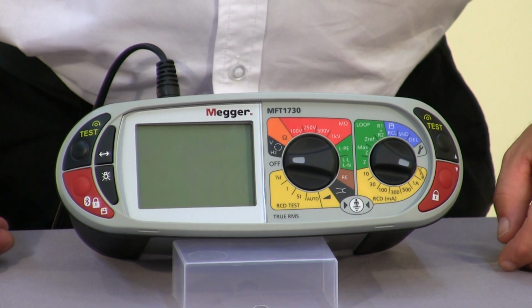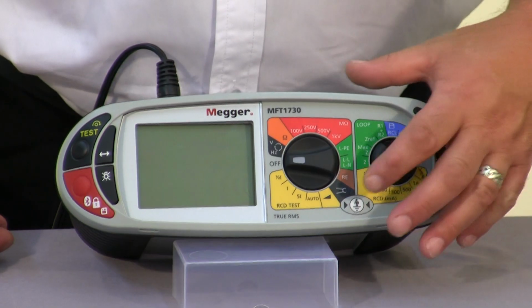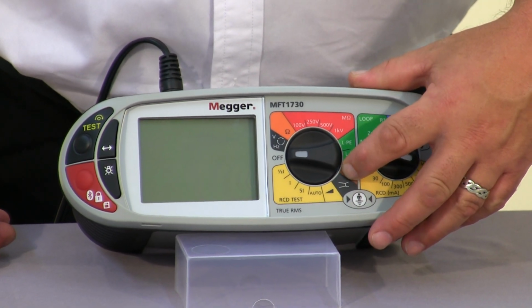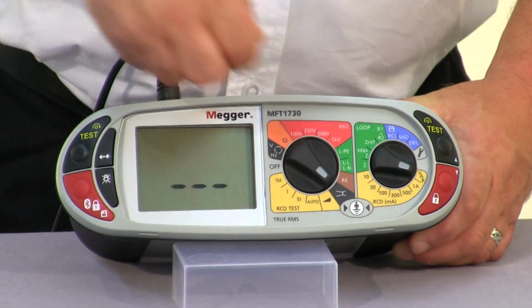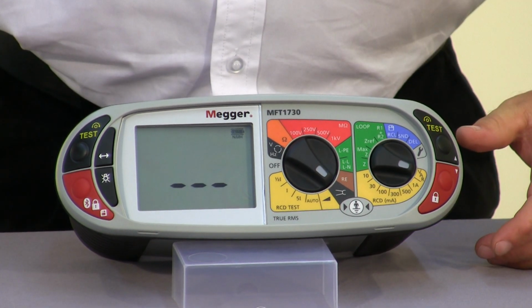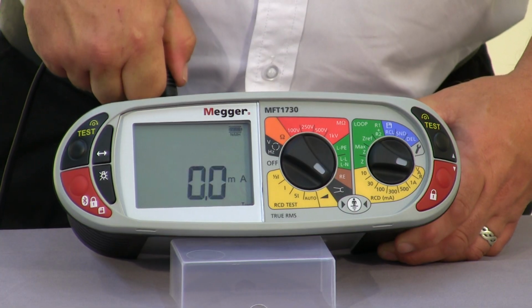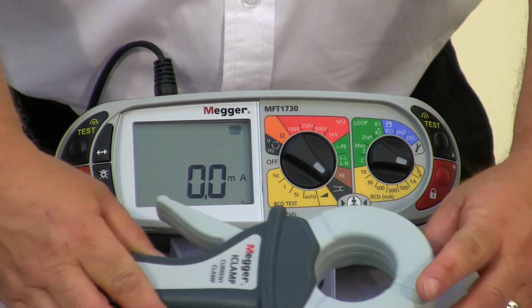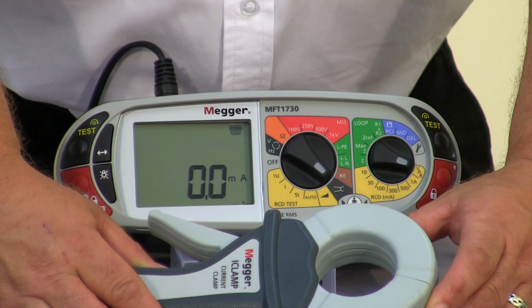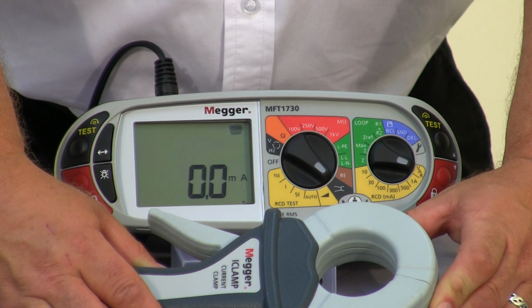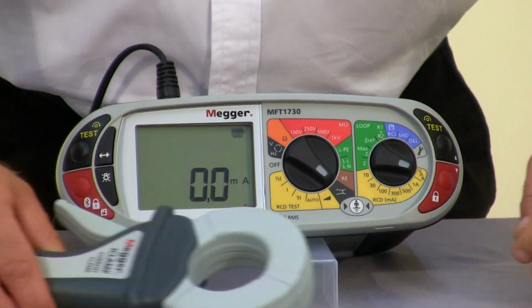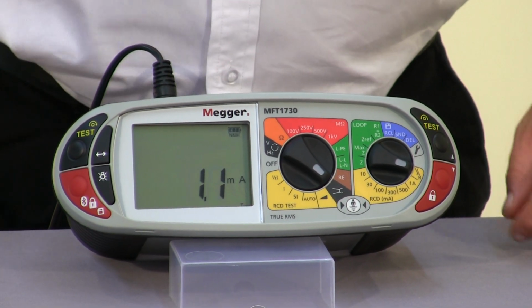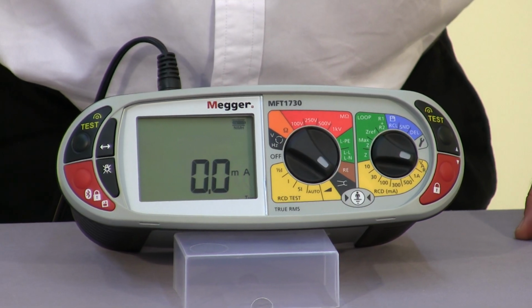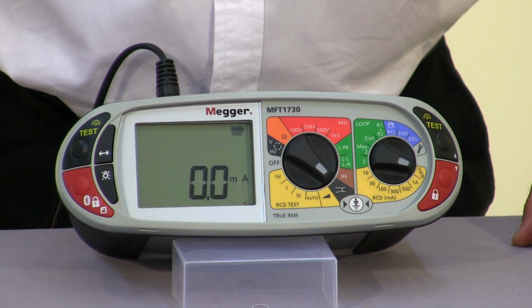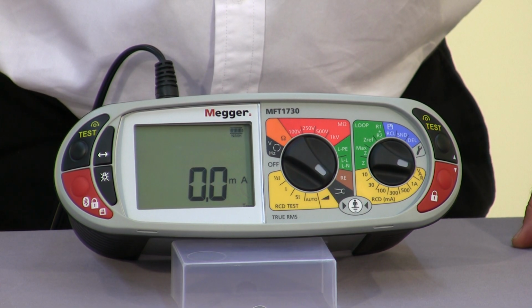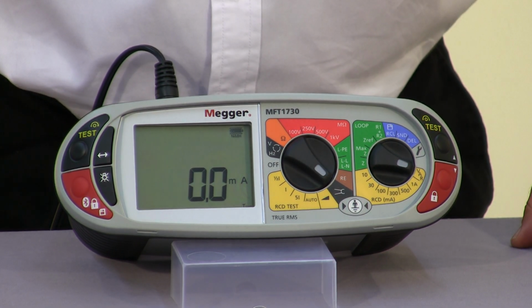The MFT1720 and 1730 models also have the facility of a CT input. Now, the current transformer that we have available as an option has a special input plug. And this unit, the Megger I-clamp, will actually measure not only high current, so you can use it for load measurements or diversity measurement, but will also measure down to very low milliamp leakage values. This means that it can be used to identify if you've got a circuit with a particularly high earth leakage in the event of nuisance tripping.